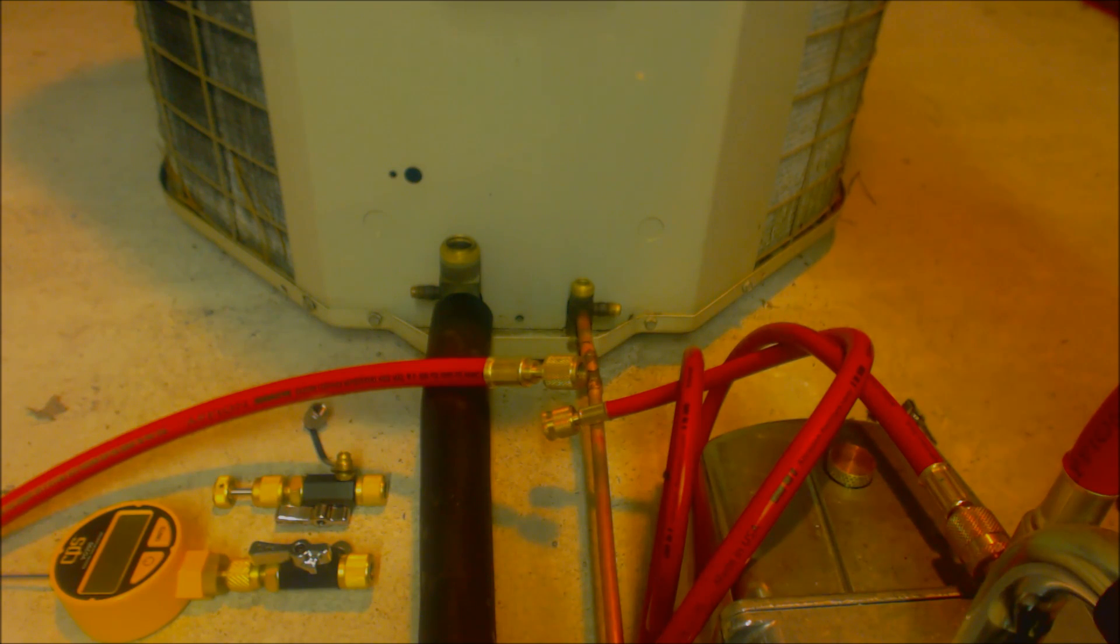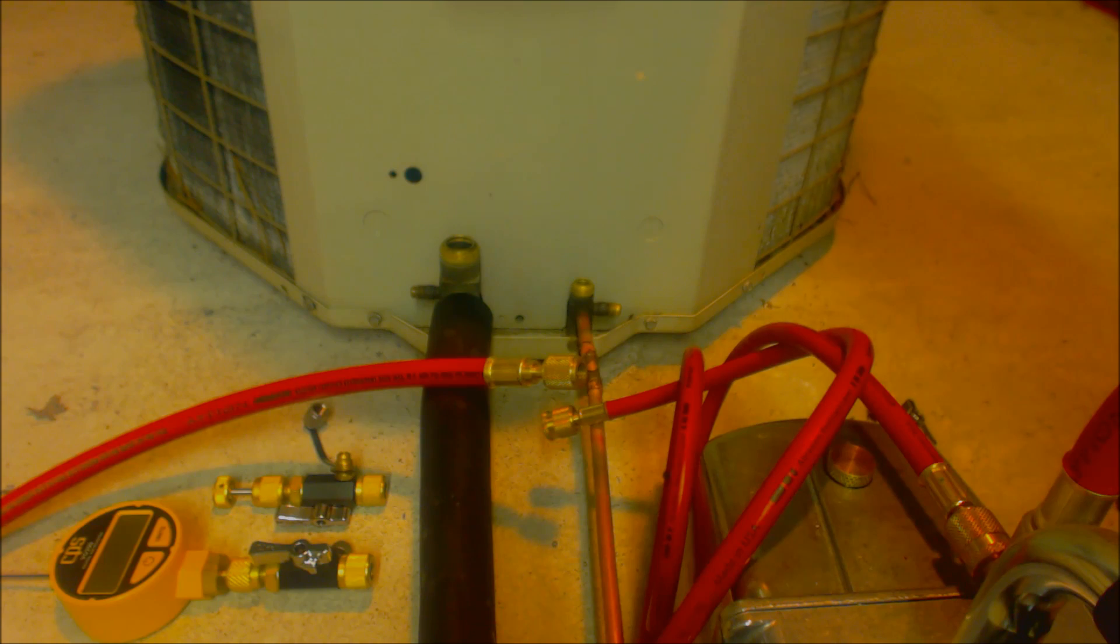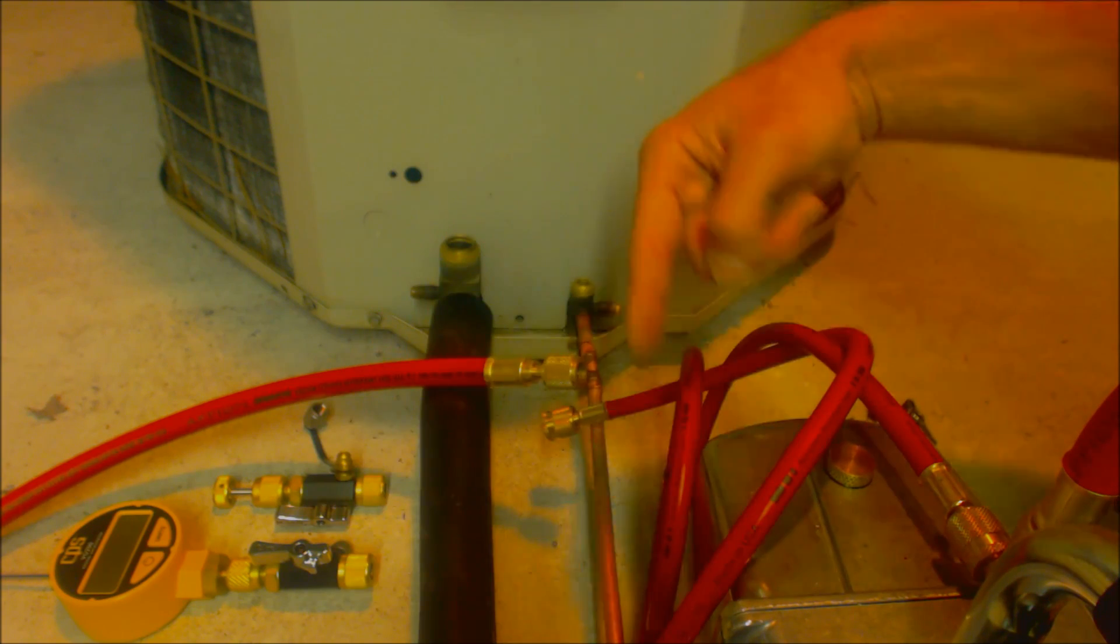On most mini split systems, the metering device is actually in the outdoor unit, so you'd only have to pull a vacuum from the one side, and most times the mini split manufacturers are only giving you a suction port, so that's okay. There is no metering device over at the wall units, so you can actually pull a vacuum from one side and pull all the way through to the other.